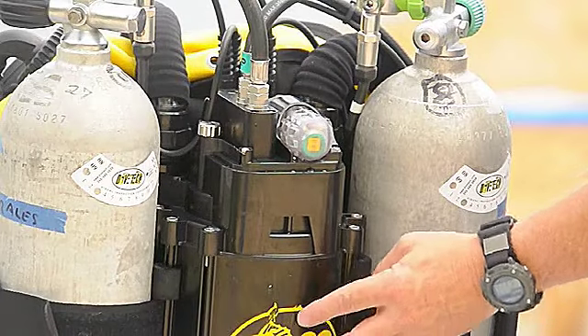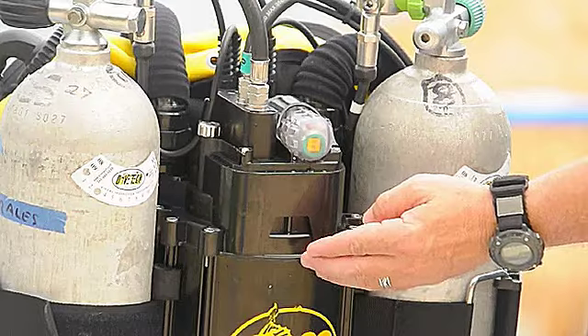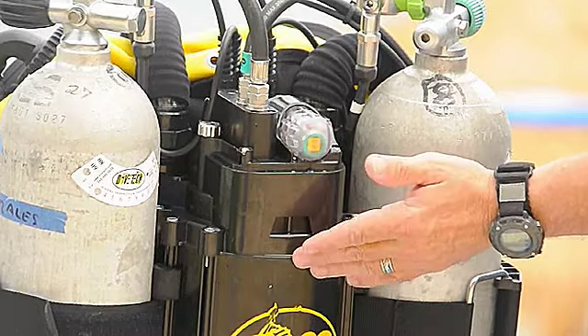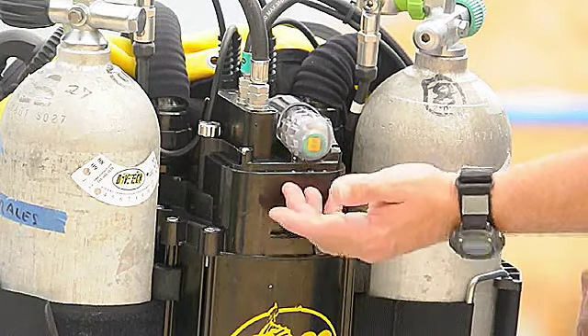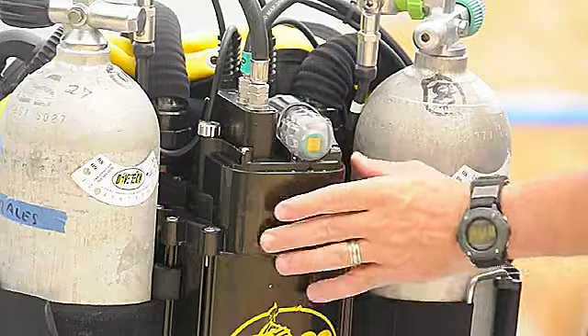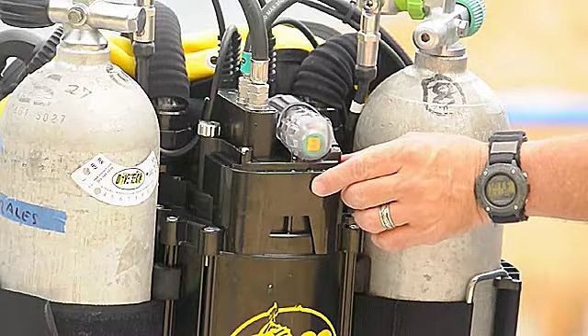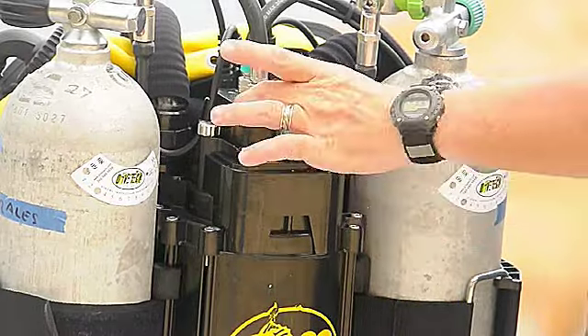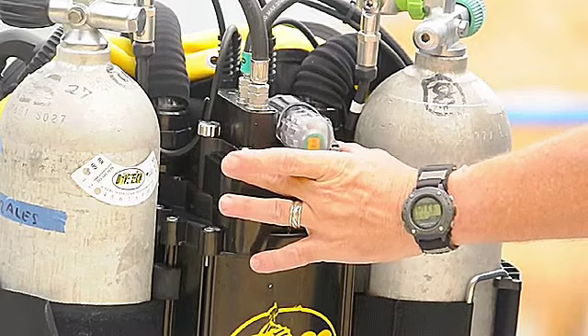So after the exhaled gas comes through the carbon dioxide absorbent canister and it's filtered and the carbon dioxide removed, that gas enters this chamber up here. This chamber right here is the oxygen sensor chamber and the electronics chamber. So this is the electronics module that sits right on top here.